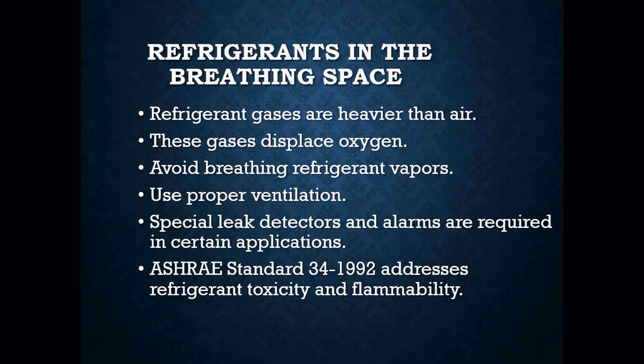Always use proper ventilation and use special leak detectors and alarms - those are required on some applications. We also use soap bubbles and electronic leak detectors to locate and pinpoint where leaks are.